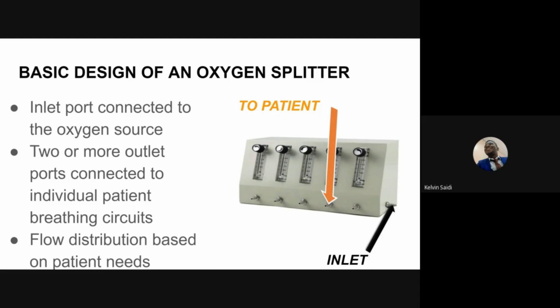The fundamental design of an oxygen splitter comprises an inlet port that connects to an oxygen source. This source can either be an oxygen concentrator, an oxygen cylinder, or piped oxygen. It also has 2 or more outlet ports that connect to individual patient breathing circuits. These splitters intelligently distribute the oxygen flow, adjusting the ratio based on each patient's unique needs.